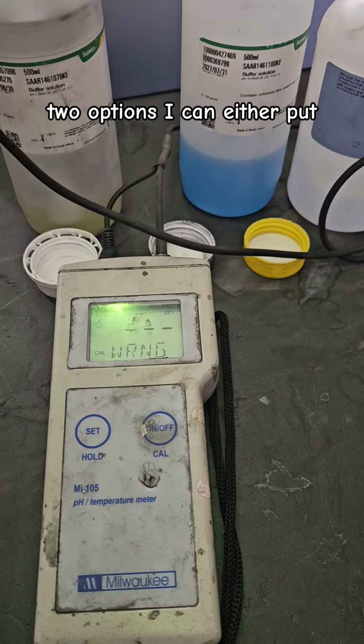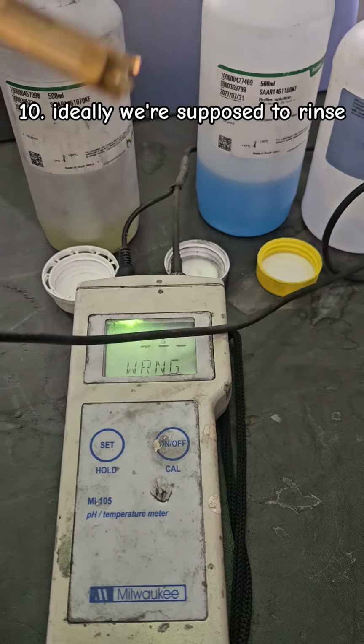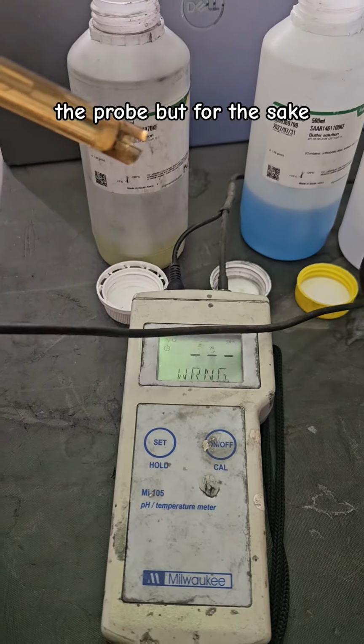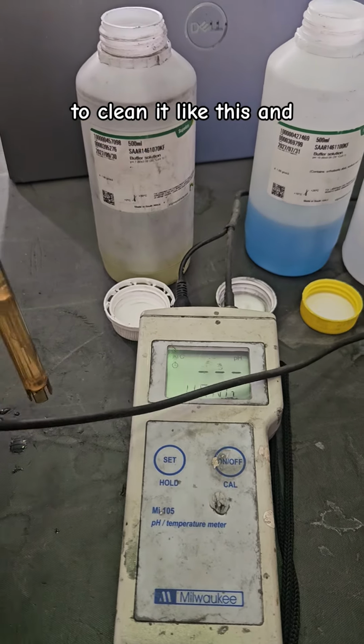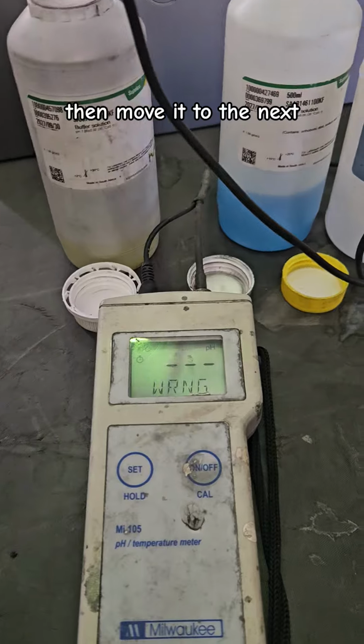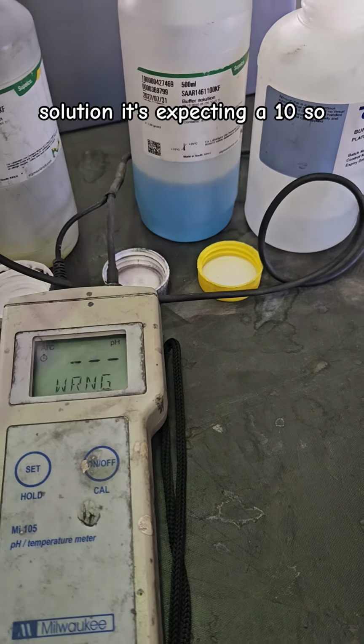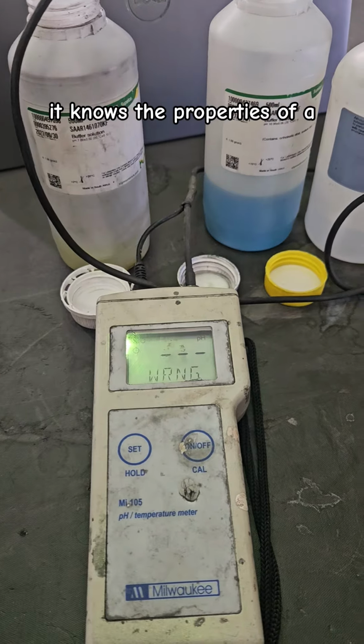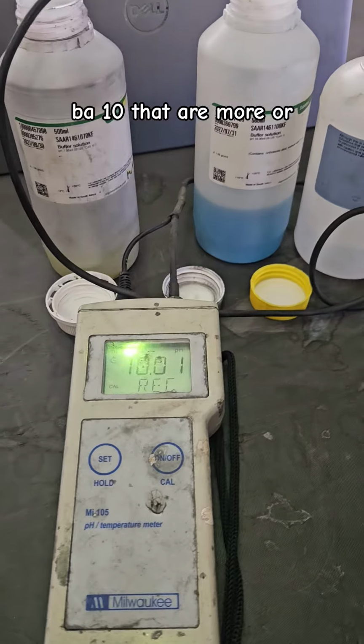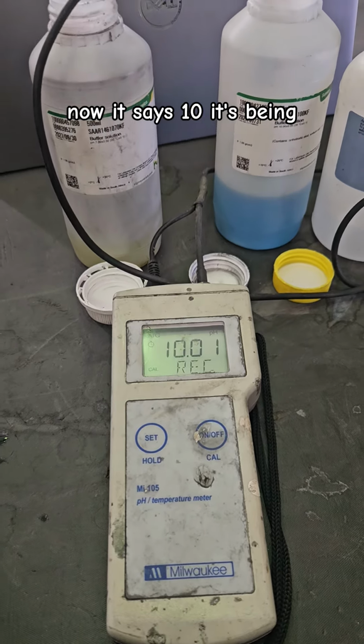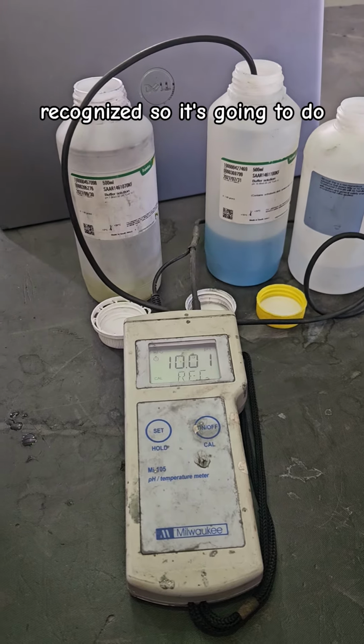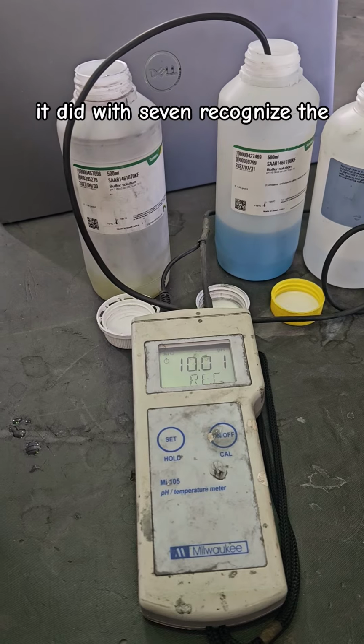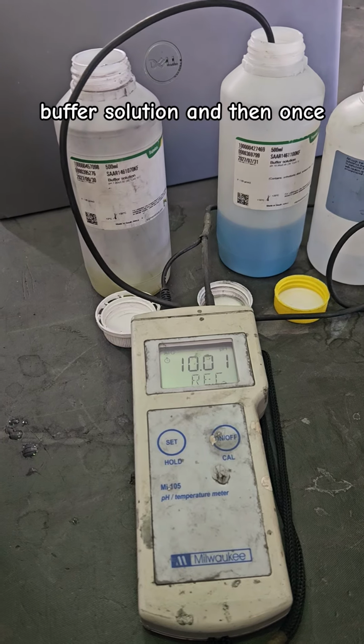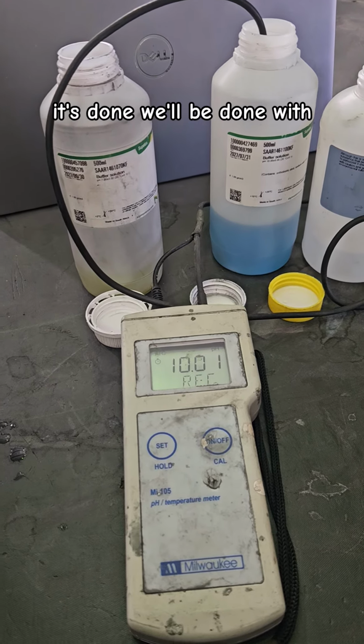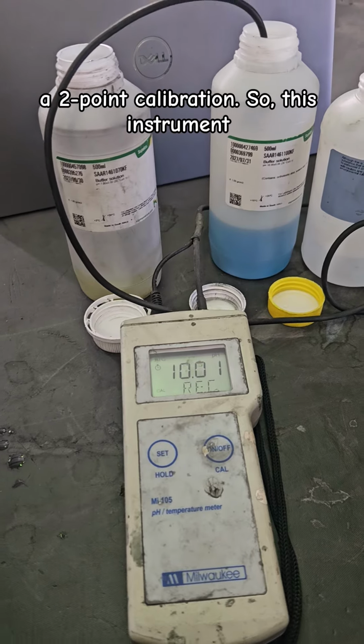I've got two options. I can either put it on a 4 or a 12. Ideally we're supposed to rinse the probe, but for the sake of this video I'm just gonna clean it like this and then move it to the next solution. It's expecting a 10, so it knows the properties of a buffer 10 that are more or less the same. You can see now it says 10. It's being recognized, so it's gonna do the same thing it did with 7. Recognize the buffer solution, and then once it's done, we'll be done with a 2-point calibration.